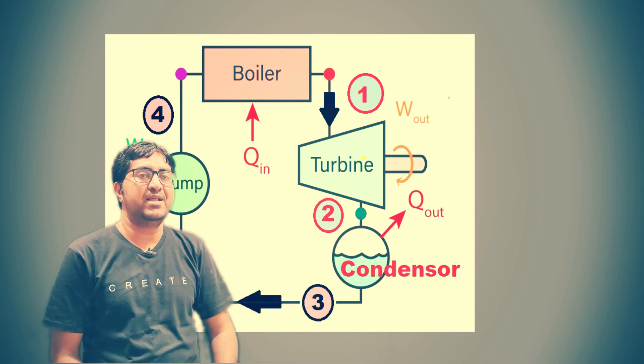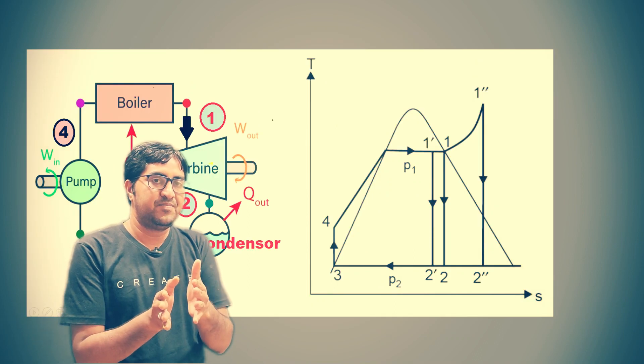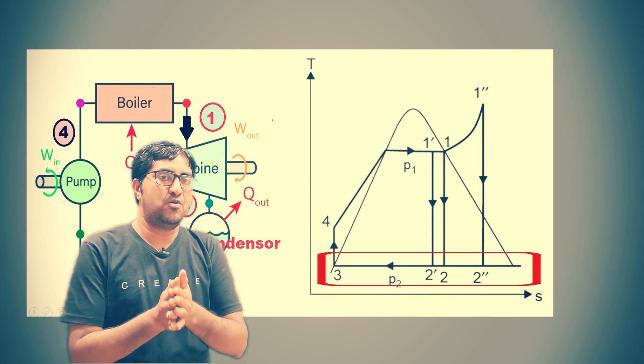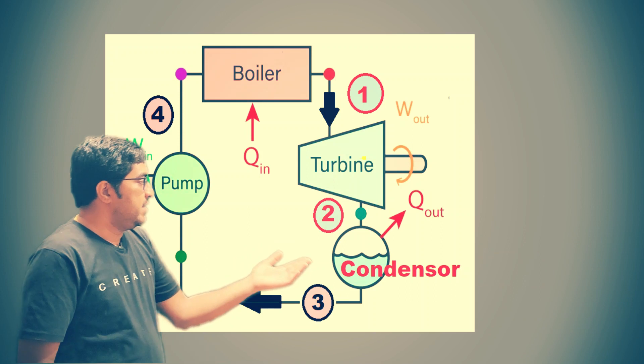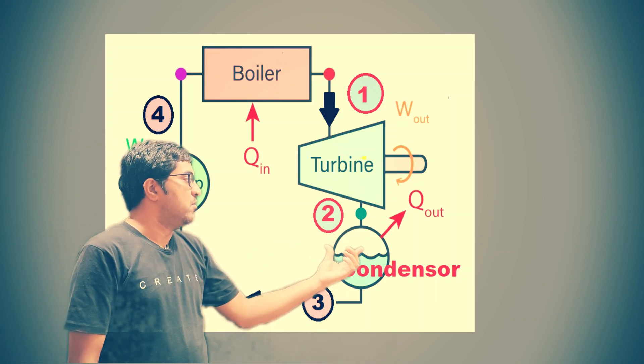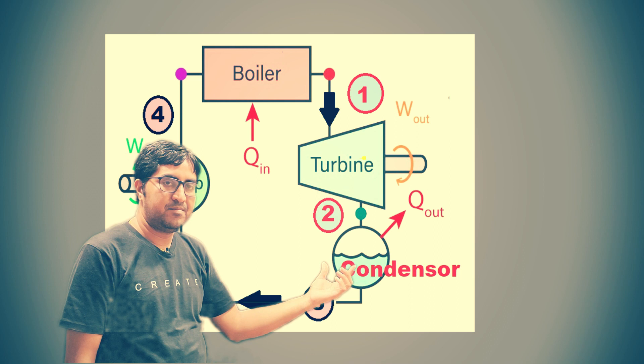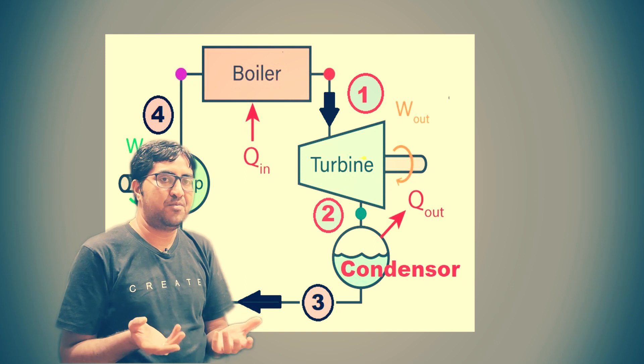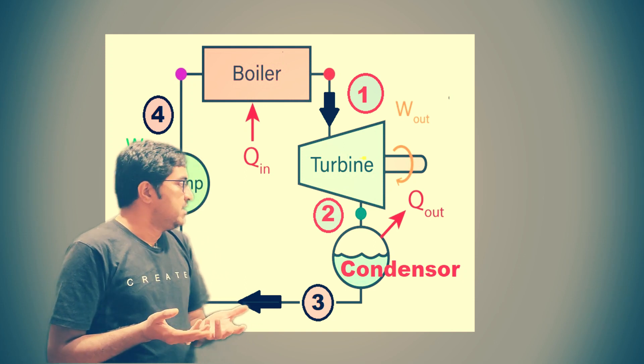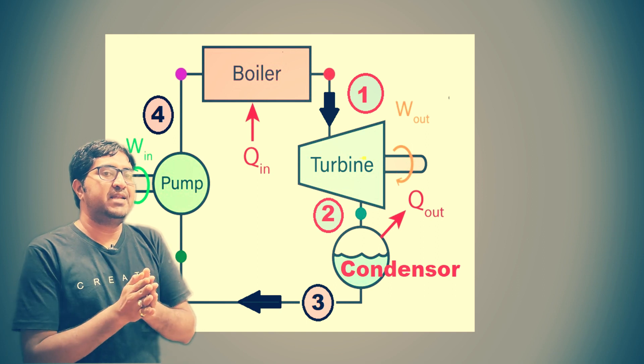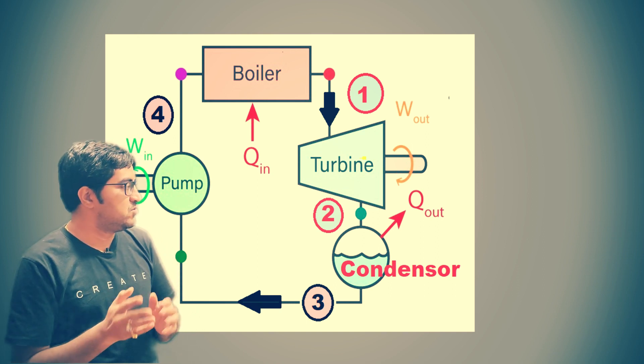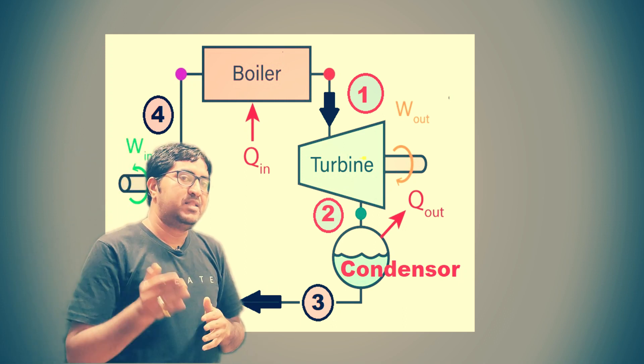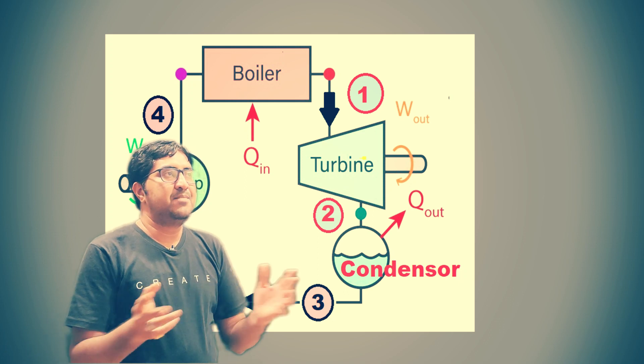In the condenser, latent heat is transferred — latent heat means there is a change of phase but the temperature remains constant, also called hidden heat. Additionally, air acts as a resistance to heat flow because its thermal conductivity is very low, making it a poor conductor of heat. So the basic need is to maintain vacuum in the condenser so that there is proper exchange of heat between the hot and cold fluid.